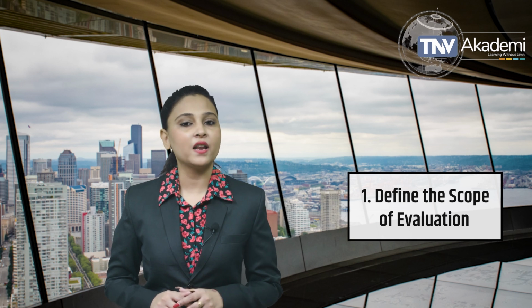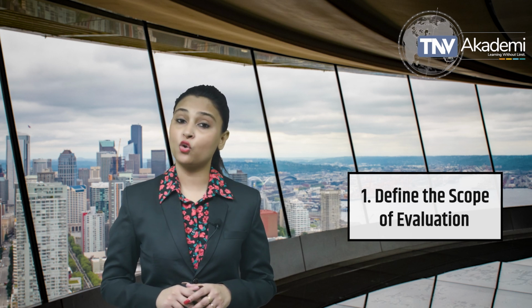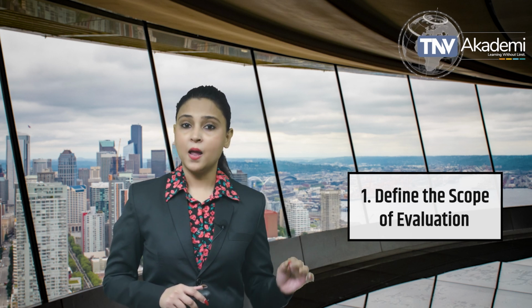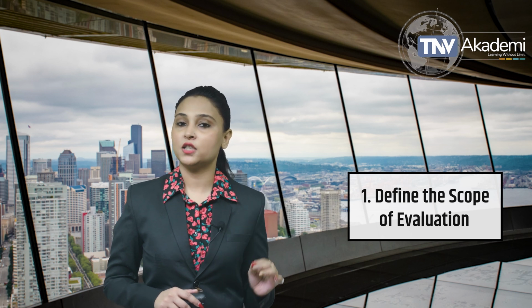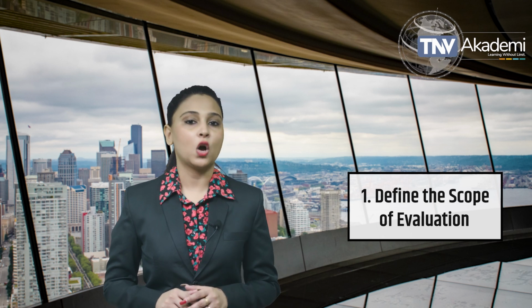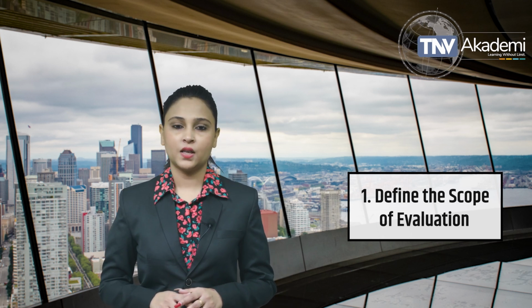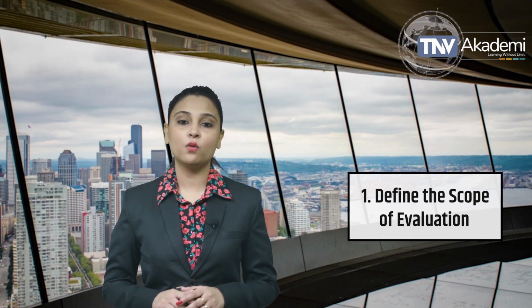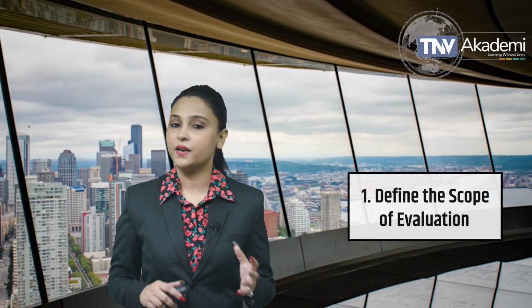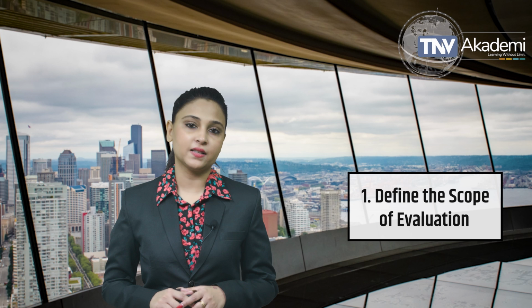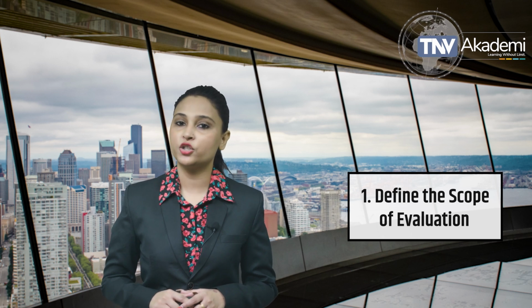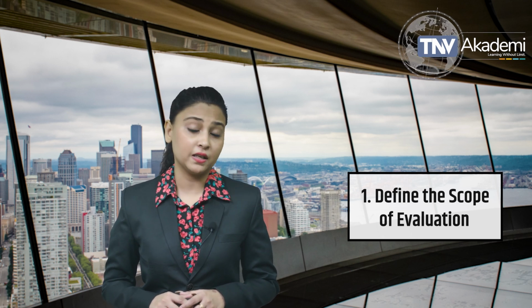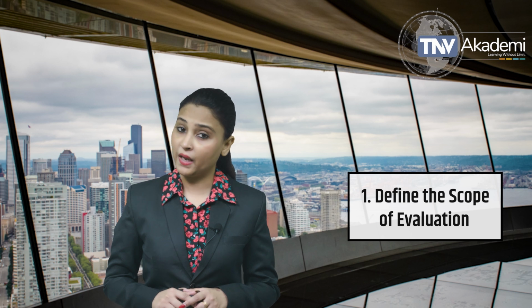Define the scope of evaluation. Start by defining the scope of the biological evaluation based on the device's intended use, duration of contact, and materials. This step helps identify what types of biological tests are necessary. For instance, devices that come into contact with blood or tissue for extended periods may need more in-depth testing compared to devices with minimal contact.